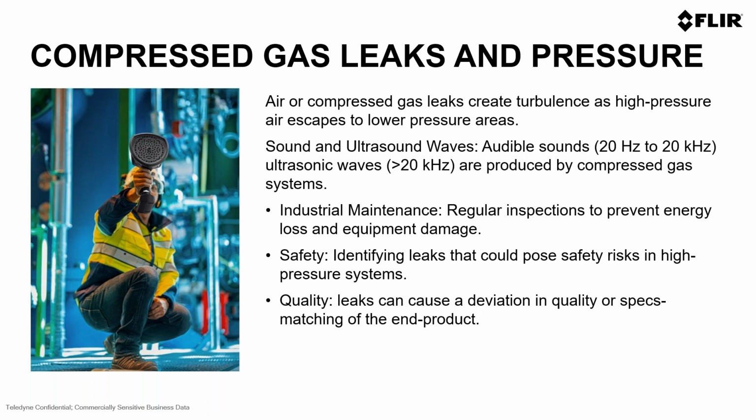That's why, for example, you can sometimes find a leak or a PD that you can hear yourself, and otherwise you will not be able to hear it. You can visit a substation and hear a sound, and it's because it's also performing in the audible range between 20 and 20,000 hertz.